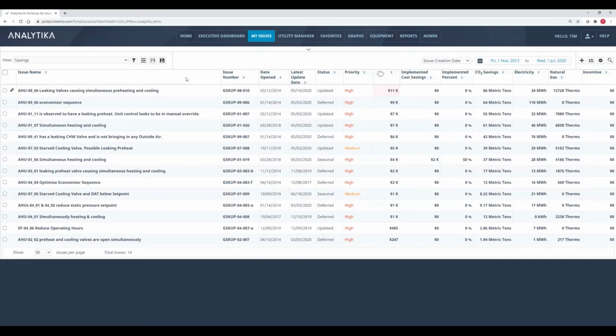Yes, a couple different ways we do that. A bunch of our algorithms look for oscillating equipment—oscillating dampers, oscillating valves—operation that is not optimal and could shorten the life of that equipment or burn out the motor. Our system finds that and flags it so preventive maintenance can be done to prolong the life of equipment that might otherwise fail prematurely. That's one way we help with preventive diagnostics.